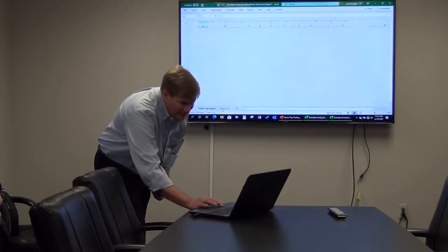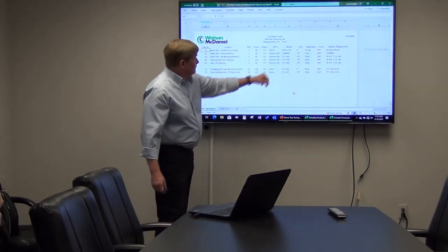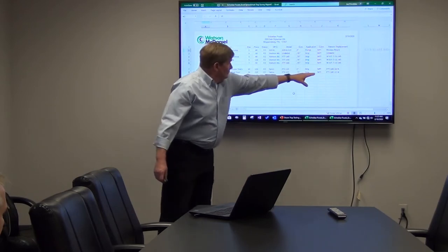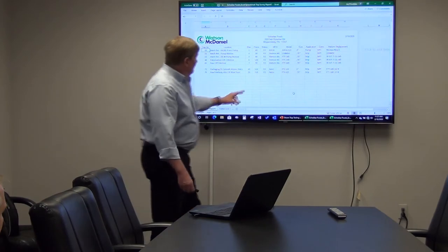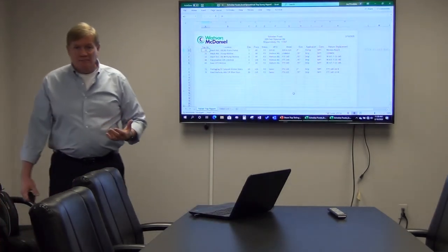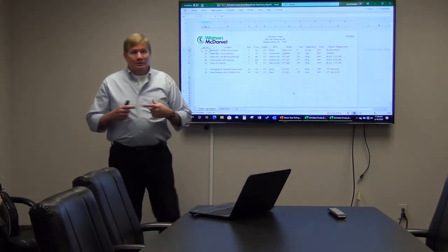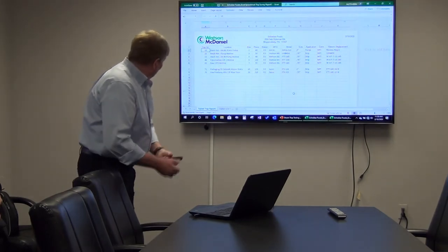Then you can extrapolate that out and say, okay, here's what I found the last time we did Schreiber Foods. Here, see the traps. Okay, Watson McDaniel, what was going on with these guys? And here's the Sarcos, and there's our replacement. That really gives the customer, as well as you guys, what we would recommend as a replacement. Generally when I'm looking at that, I'm going to select something that matches the capacity of the existing trap, as well as the piping connections, so they don't have to make piping changes. It's going to be a drop-in replacement.